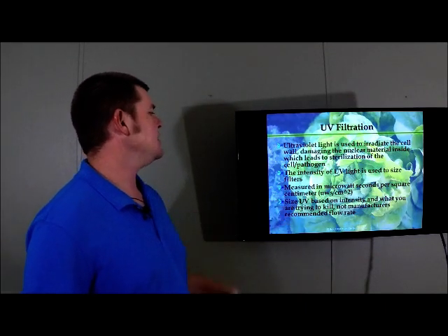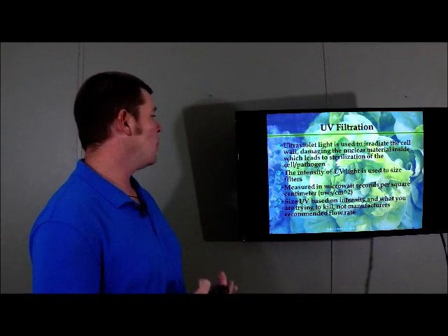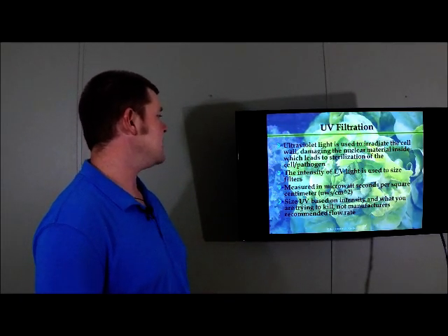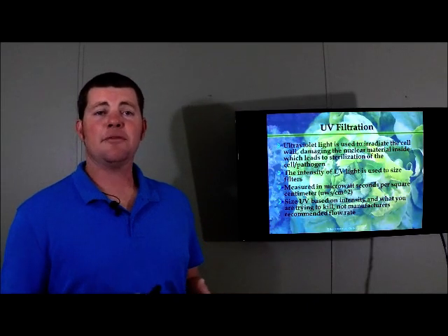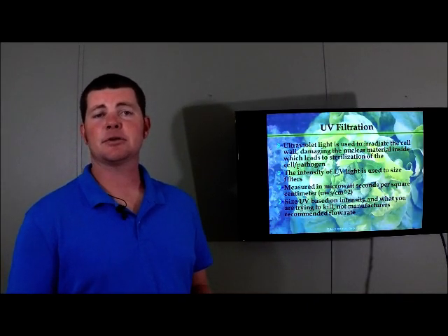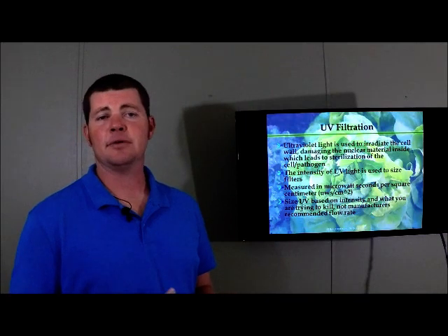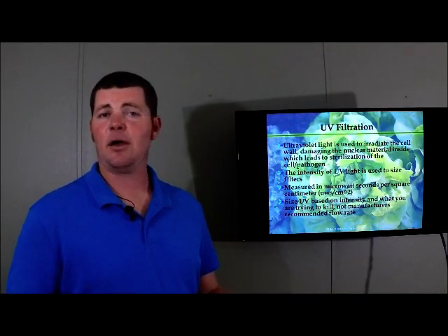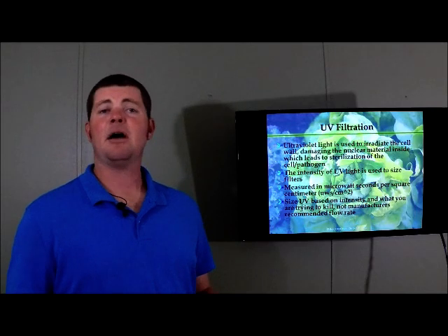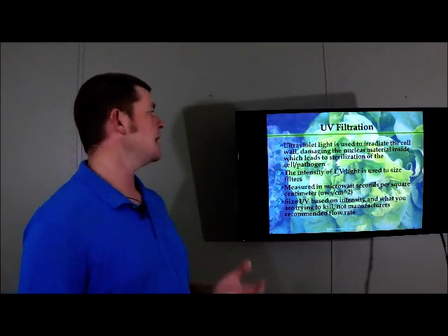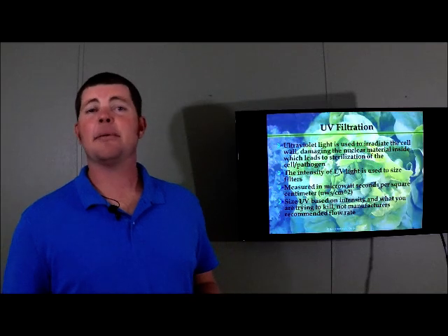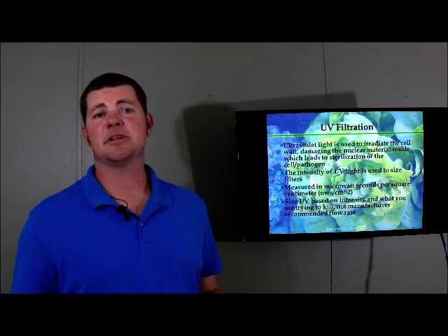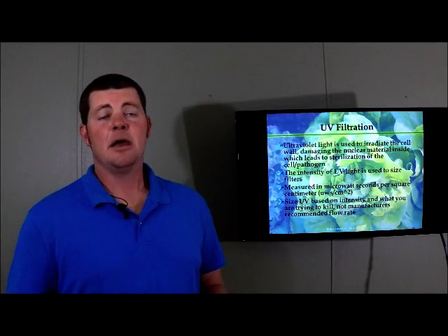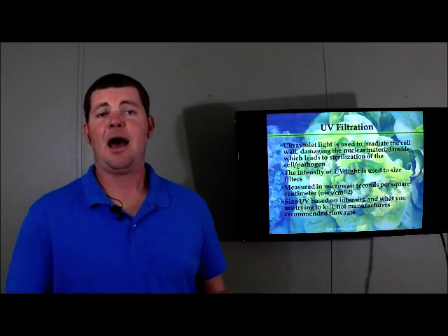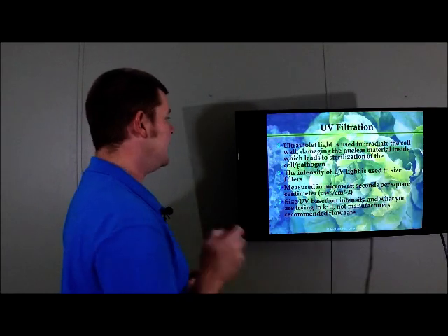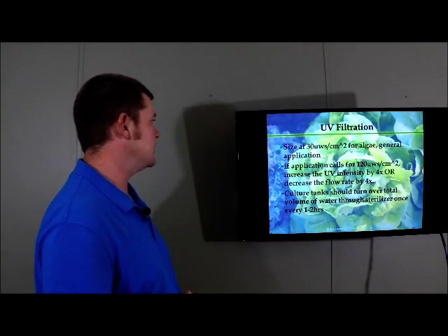And we size the UV based on the intensity and what we're trying to kill, not the manufacturer's recommended flow rate. So if you blindly go out and try to buy a UV filter, you're going to see a bunch of different diameter UV filters, a bunch of different intensity lights, and they'll have flow rates on them. If you just pick one off of the flow rate, you're probably going to get sized at 30,000 microwatts per square centimeter, or maybe even 15,000, because it looks real attractive to put a higher flow rate on a smaller light. But that's not the case. We want to do the math on this stuff.